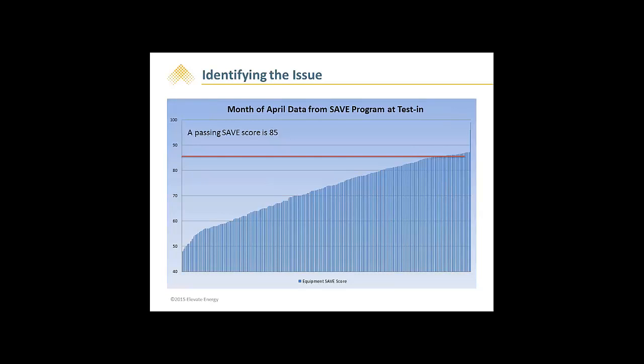A SAVE score is like a conversion efficiency ratio that basically compares energy out to energy in. Using measurements taken in the field to assess current operating efficiency, this month only 16% of systems that were tested passed to the SAVE standard. This is a significant sampling size, which is backed by a DOE study titled Energy Savings from System Efficiency Improvement in Iowa's HVAC SAVE program, where in this study the results were very similar.